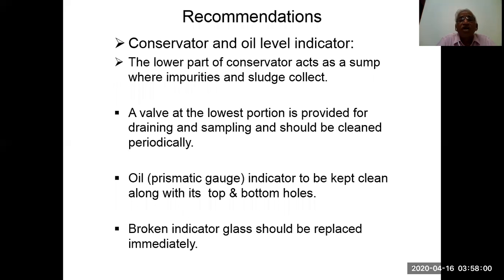Recommendations: conservator and oil level indicator. The lower part of the conservator acts as a sump where impurities and sludge collect. A valve at the lowest portion is provided for draining and sampling, and it should be cleaned periodically. All prismatic gauge indicators are to be kept clean along with their top and bottom poles. Broken indicator glass should be replaced immediately.